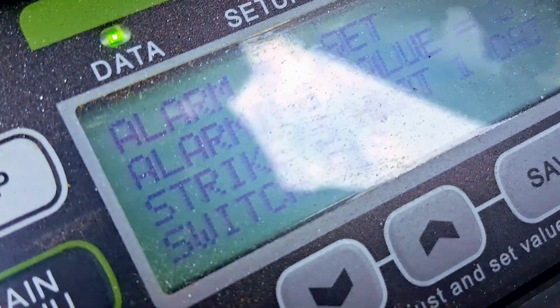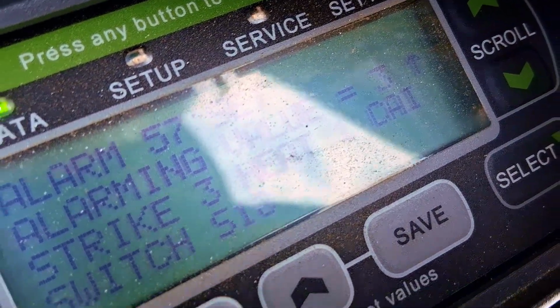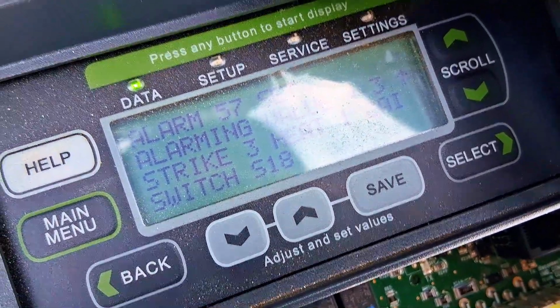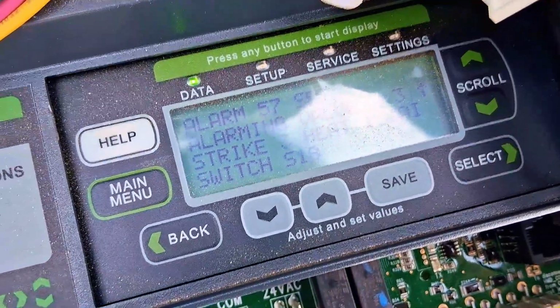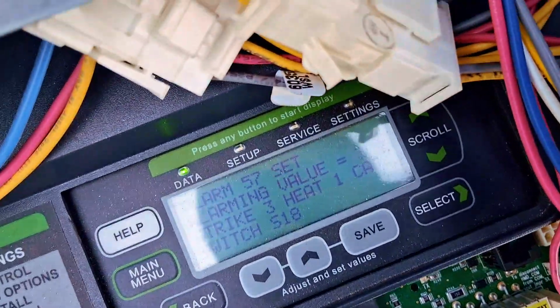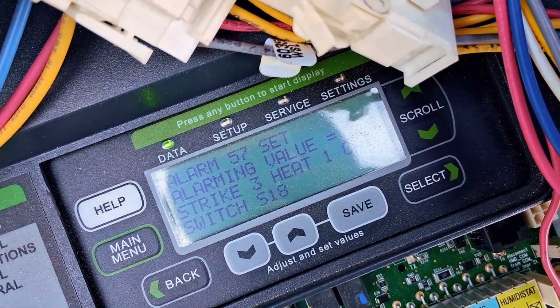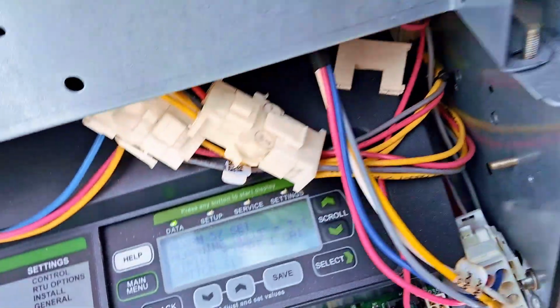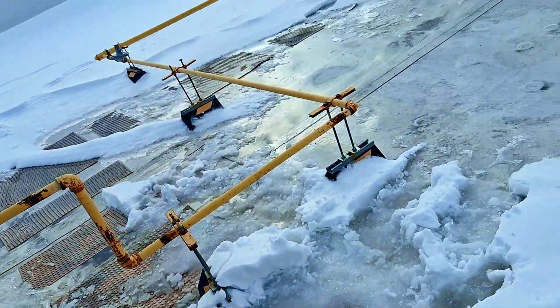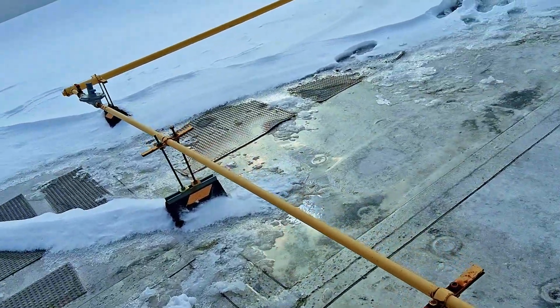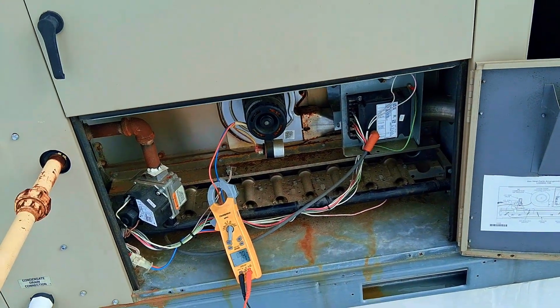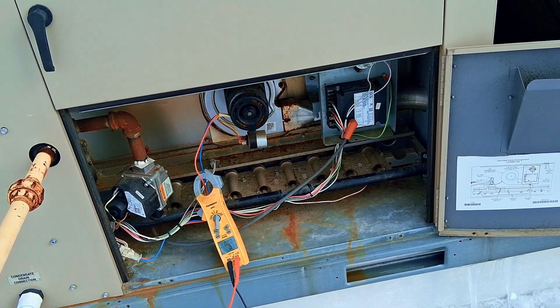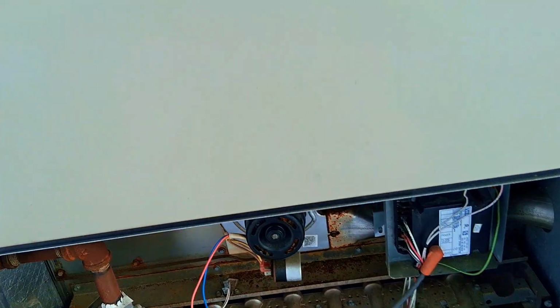Alright, so now it's giving me a strike 3 heat, 1 CAI switch S18. That's basically saying the inducer motor is not proving. So what I did was amp out the inducer motor while it was running, and I see there's a lot of overamping. I've got a feeling the inducer motor is not pulling enough air through here, and it's dying out.